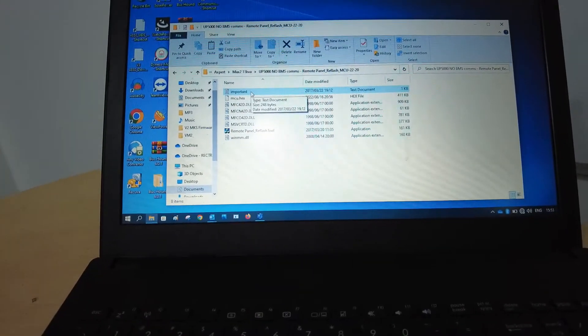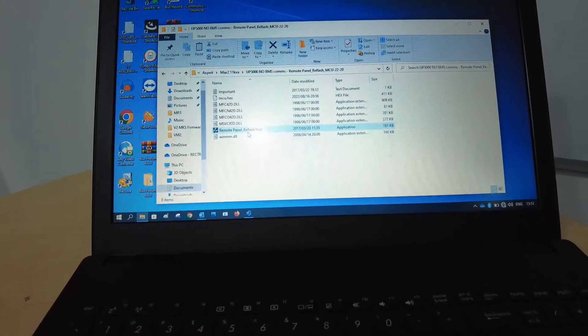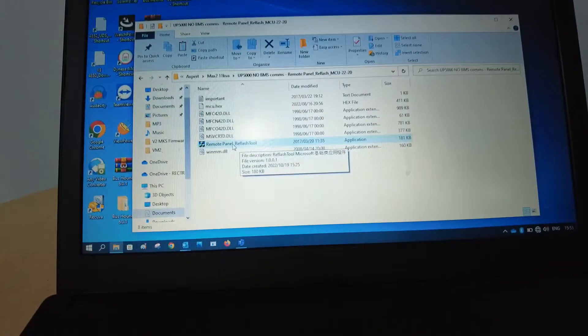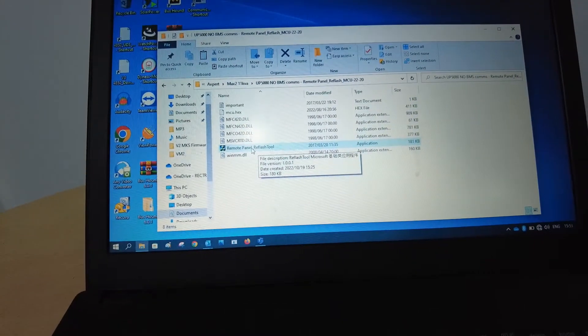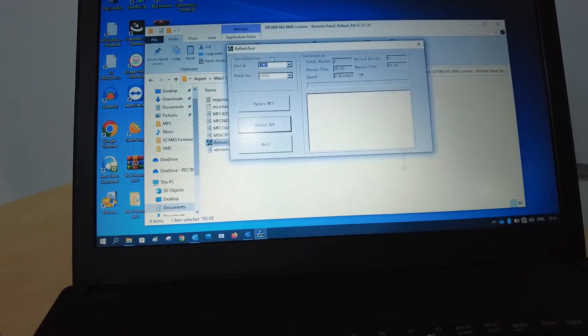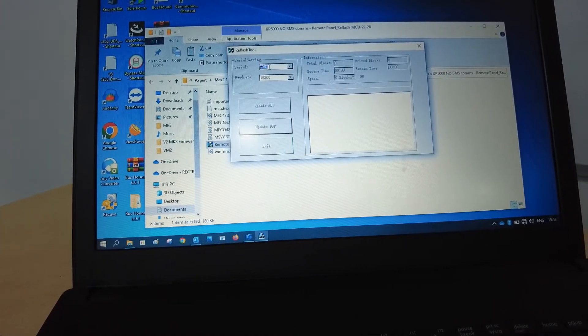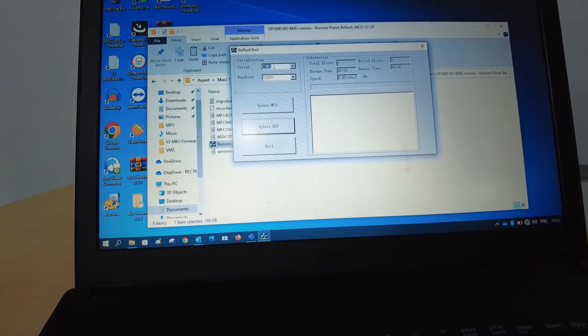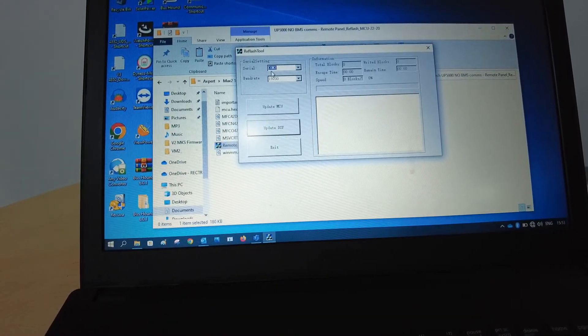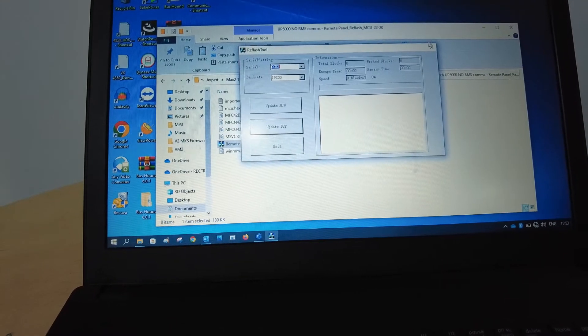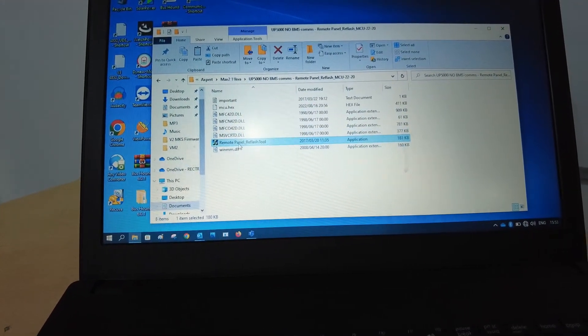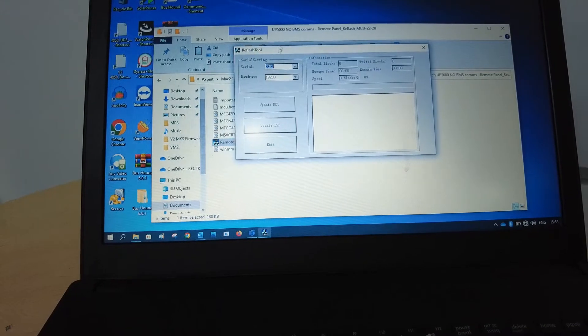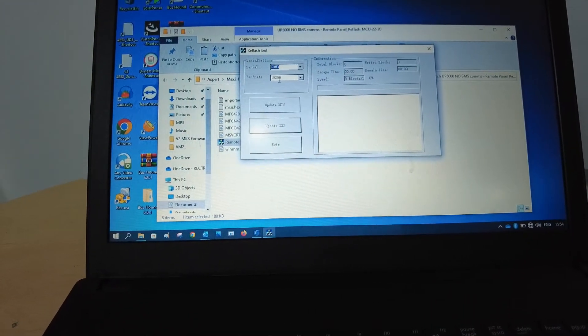After you've received the firmware and you open up the file, you will notice inside the file you will have this remote panel reflash tool. Click on that. Make sure your COM port at the top automatically detects. It might sometimes happen, but if it does not automatically detect I find it better to just close the program and open it again until it automatically detects. If it automatically detects, it's ready to go.